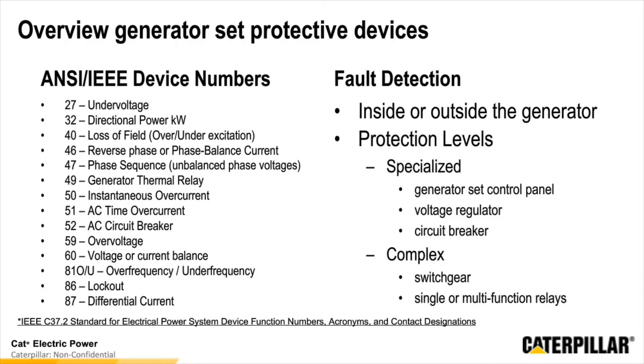There's also going to be multiple levels of protection within our system. We're going to have specialized controls such as the generator set control panel, the voltage regulator, or the circuit breaker. There's also complex controls that you'll find within your switchgear or within a single or multifunction relay, depending on how your application is designed. For our discussion today, we're going to focus, as we talked about, primarily on the generator's protection. So we're going to look at the protectives associated with our generator set control panel and with the circuit breaker. These are going to be the 50 instantaneous overcurrent, the 51 AC time overcurrent, and the 52 AC circuit breaker. And you'll see those designations by their device number in the drawing as we go forward.